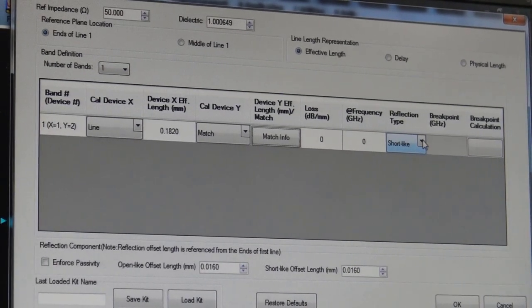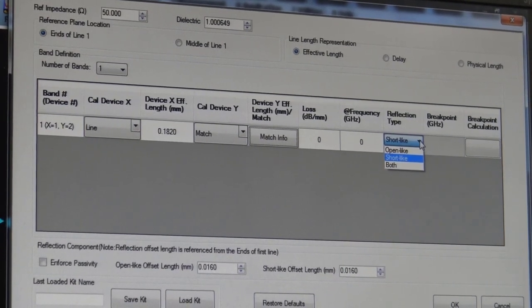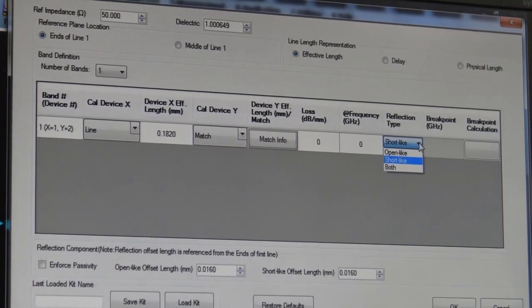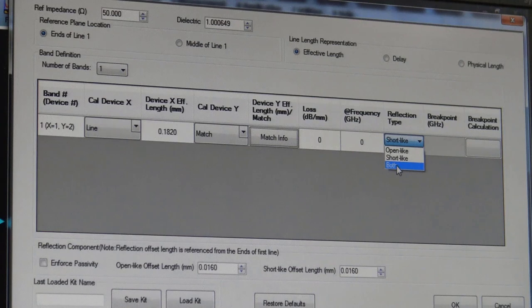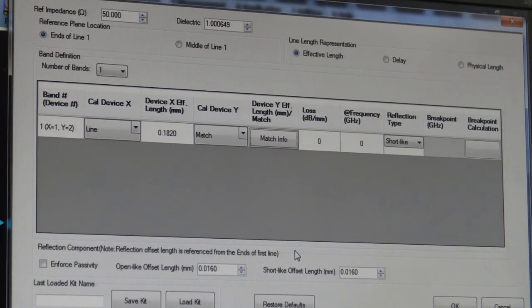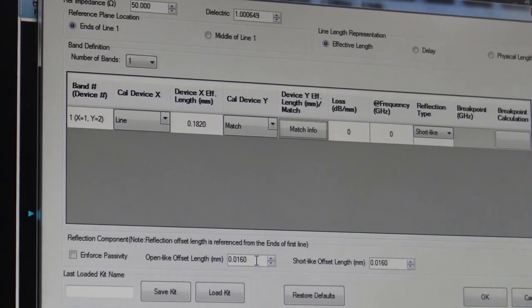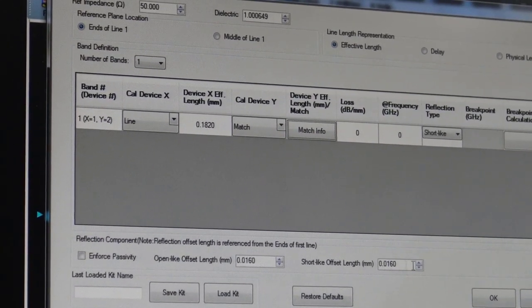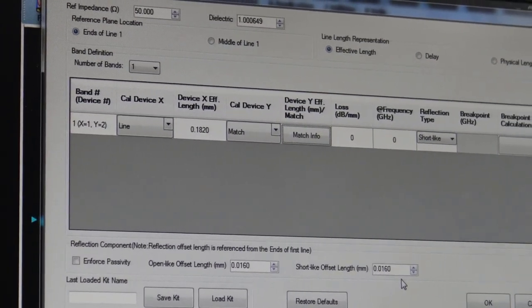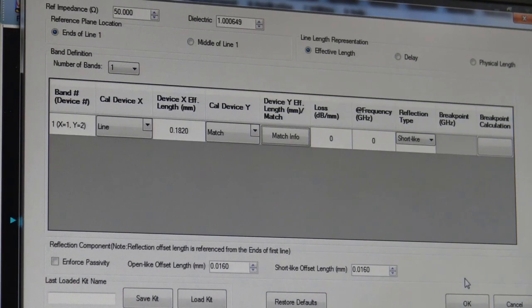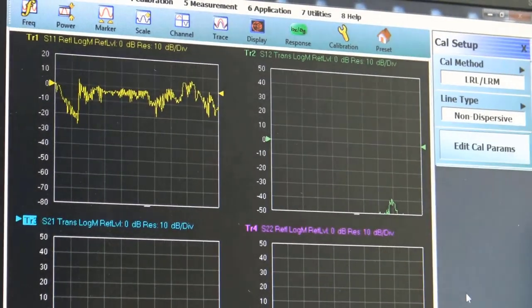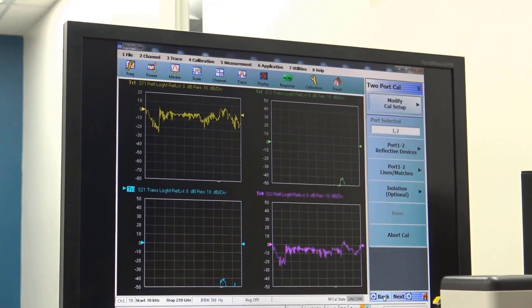We just now want to determine what type of reflect that we're going to use, either an open or a short. It doesn't have to be perfect. It's just an open like or short like. You can also include both. So you can include two different reflection types. That's our advanced LRM capability. In this case, we'll just be doing the short. Now to finalize the description of the standards we're using, we can enter the offset lengths for the open and the short. In this case, it's 16 micron length to the shorts and the opens. And that's what's entered here. So now we're set up. We have all the information we need that defines this calibration substrate. We'll click OK, and then go back to our calibration menu.